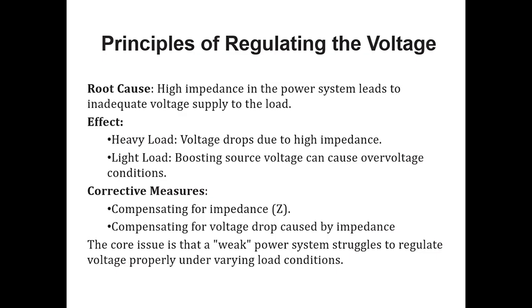Now what corrective measures can we take to regulate the voltage? What different things do we need to add or incorporate so that the voltage becomes a regulated one? The first thing we are going to discuss is compensating for impedance Z. That means we have to use a compensator, or think about the impedance and how much maximum load there will be, and we are going to compensate this impedance, that is, compensate for the voltage drop caused by the impedance. Again, how are we going to compensate that voltage drop? We are going to think in that way.